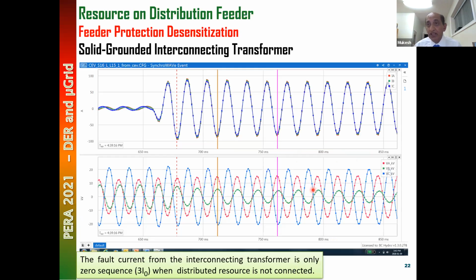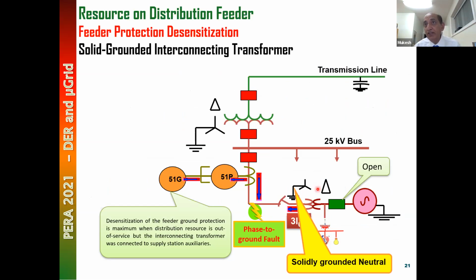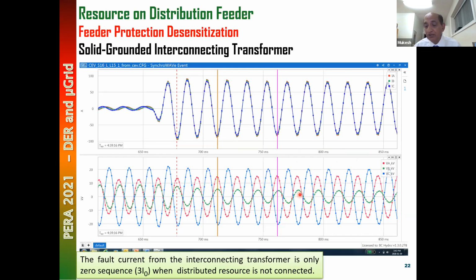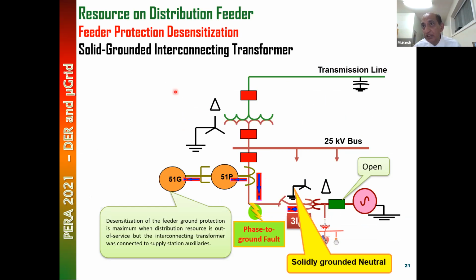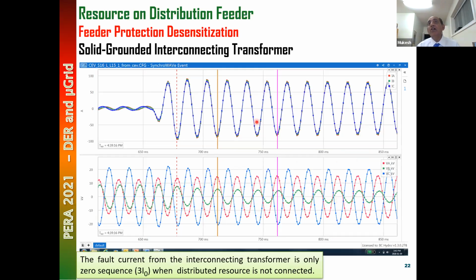This is a fault record when there's a line to ground fault current here, and you will see three-phase currents coming out of here, and you'll see what interesting three-phase current coming out of here. I'm going to show three-phase voltages here, and three-phase current when no source is connected here, when this breaker is open. Look at the current. All three currents are in phase. A, B, C currents are in phase because there's no positive sequence voltage source behind it. The delta transformer is circulating a zero sequence current and sucking up all the current from the utility side and providing a zero sequence source. This is how it is.